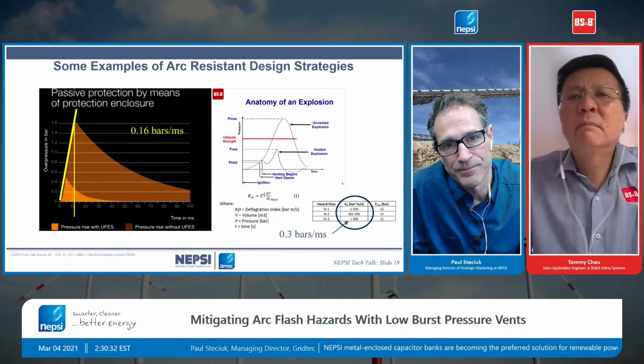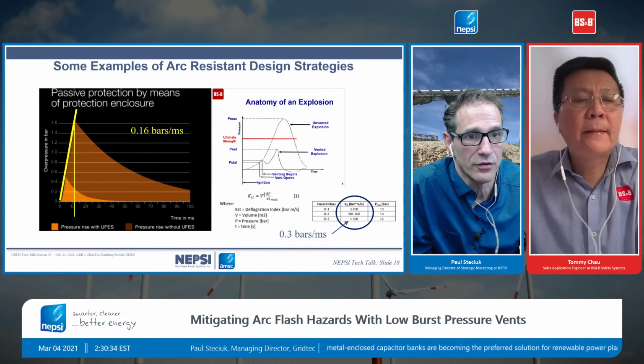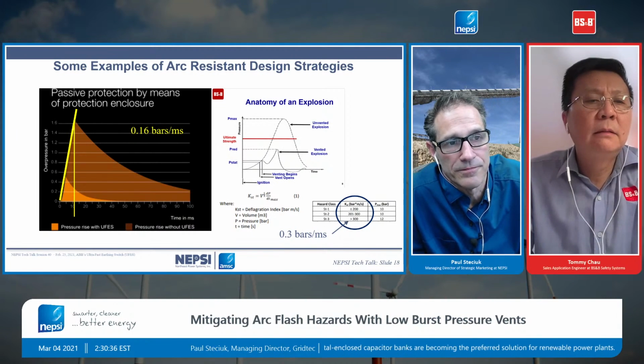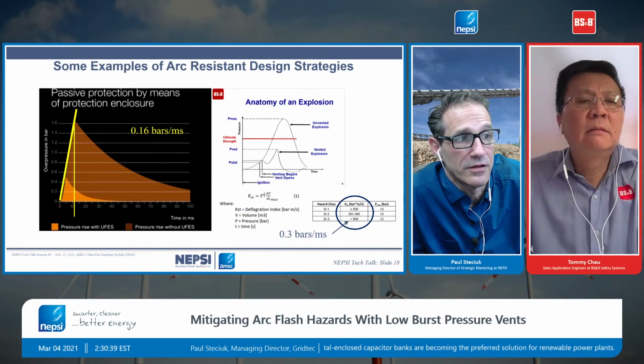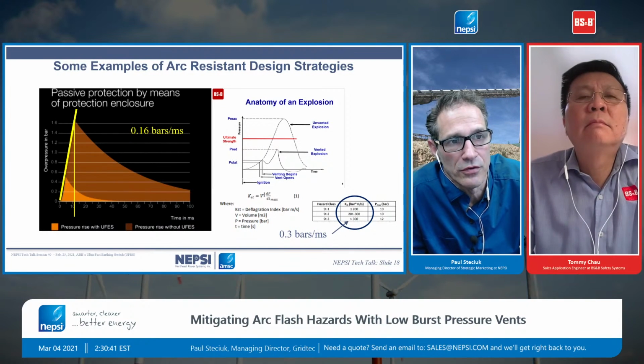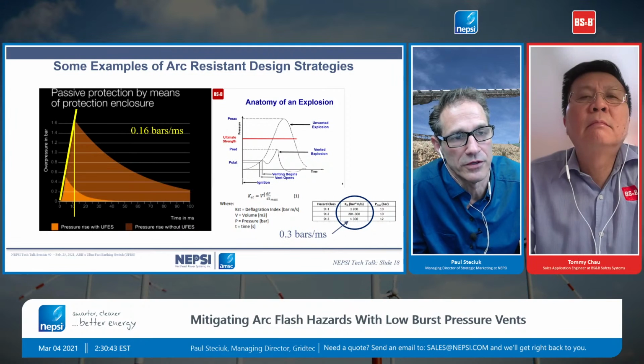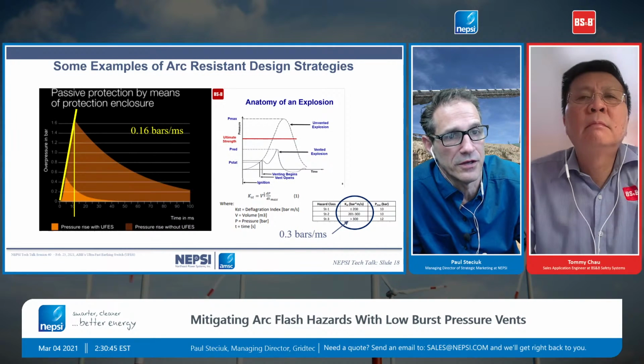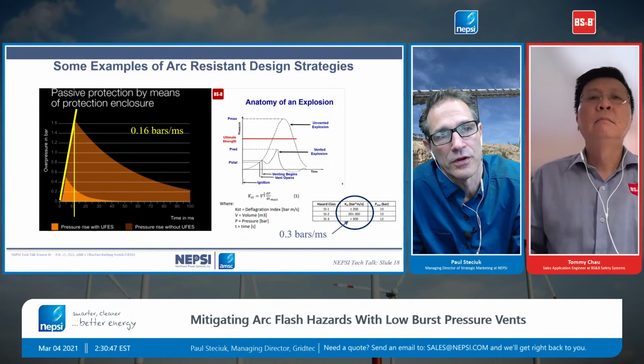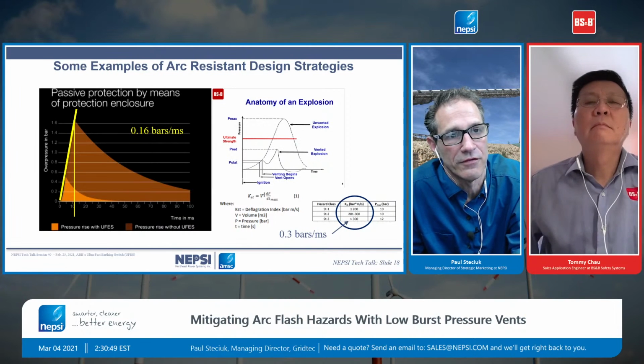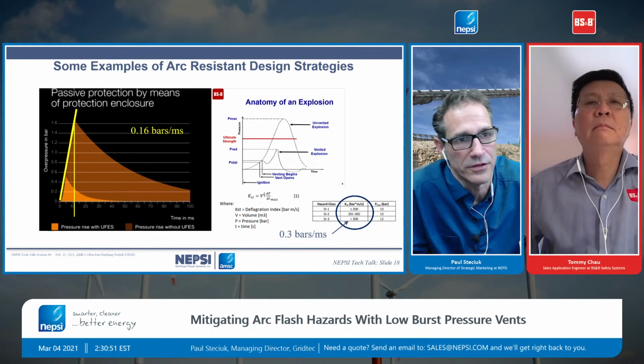So this is one of the reasons we went towards using these low burst vents: they can be effective in reducing the pressure buildup. Although NFPA 68 is addressing dust, we're cross-applying it to this arc flash event and the pressure buildup in the enclosure.